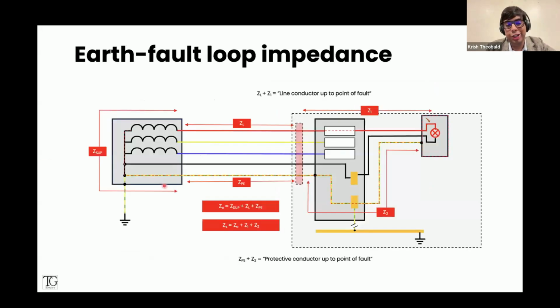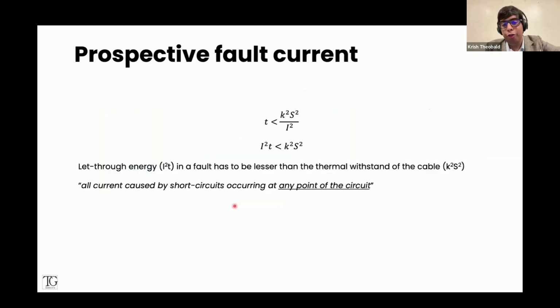In an installation, we need to know the Z supply, ZL, Z1, Z2, and ZP. And essentially, you need to know all of this to calculate what your earth fault loop impedance is here. So when a fault occurs here, the magnitude of fault current is dependent on all of these separate factors. Prospective fault current, I squared t shall be less than k squared S squared. So the amount of let-through energy has to be less than the cable can withstand, and it has to be ensured for short circuits occurring at any point in the circuit.